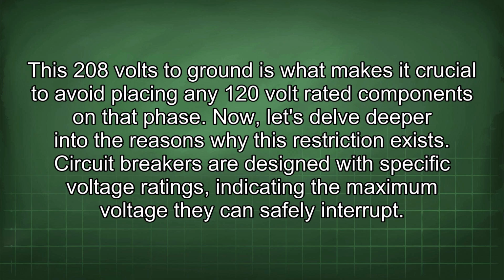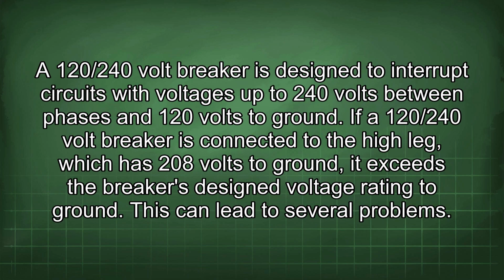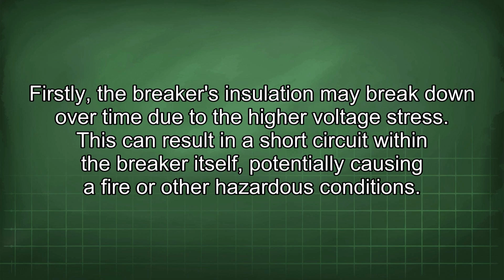Circuit breakers are designed with specific voltage ratings, indicating the maximum voltage they can safely interrupt. A 120/240 volt breaker is designed to interrupt circuits with voltages up to 240 volts between phases and 120 volts to ground. If a 120/240 volt breaker is connected to the high leg, which has 208 volts to ground, it exceeds the breaker's design voltage rating to ground. This can lead to several problems. Firstly, the breaker's insulation may break down over time due to the higher voltage stress. This can result in a short circuit within the breaker itself, potentially causing a fire or other hazardous conditions.